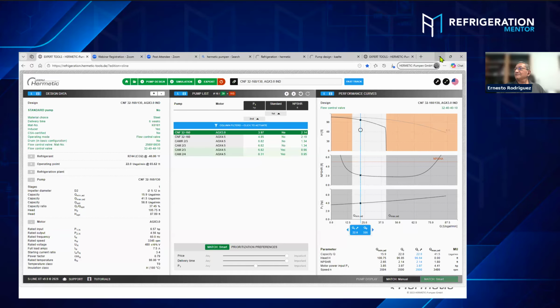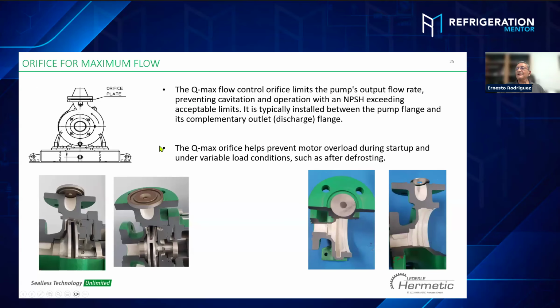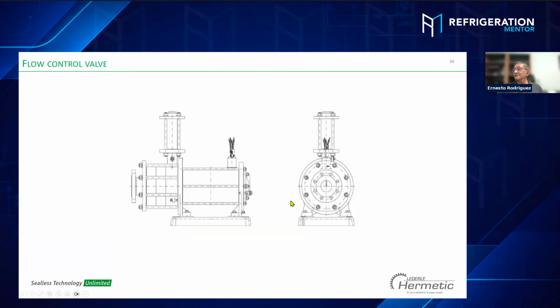Okay. Let's go back to my presentation. I talked about Qmin. This is the Qmin, Qmax. We control with the orifice, we control the flow of the pump to prevent it from going to the orange area. The orifice is already sized for the capacity. For example, in the program, for some flow, 60 gallons per minute, this orifice is sized to work with 60 gallons per minute. That is the best way to work, and you do not want to exceed the mass flow, to avoid overheating the motor and maintain your system running perfectly.